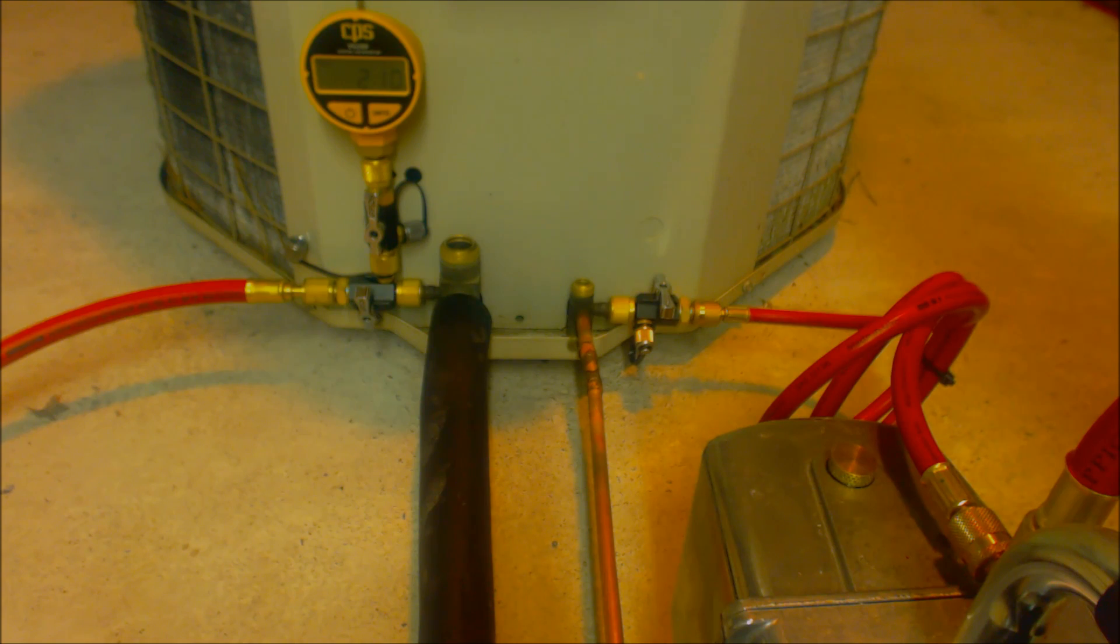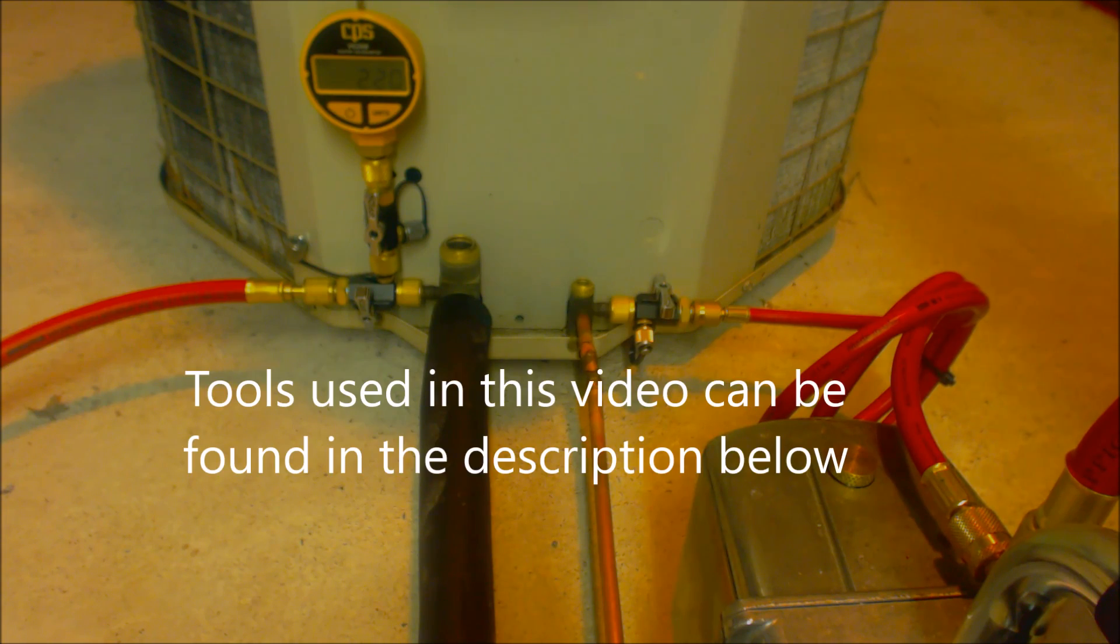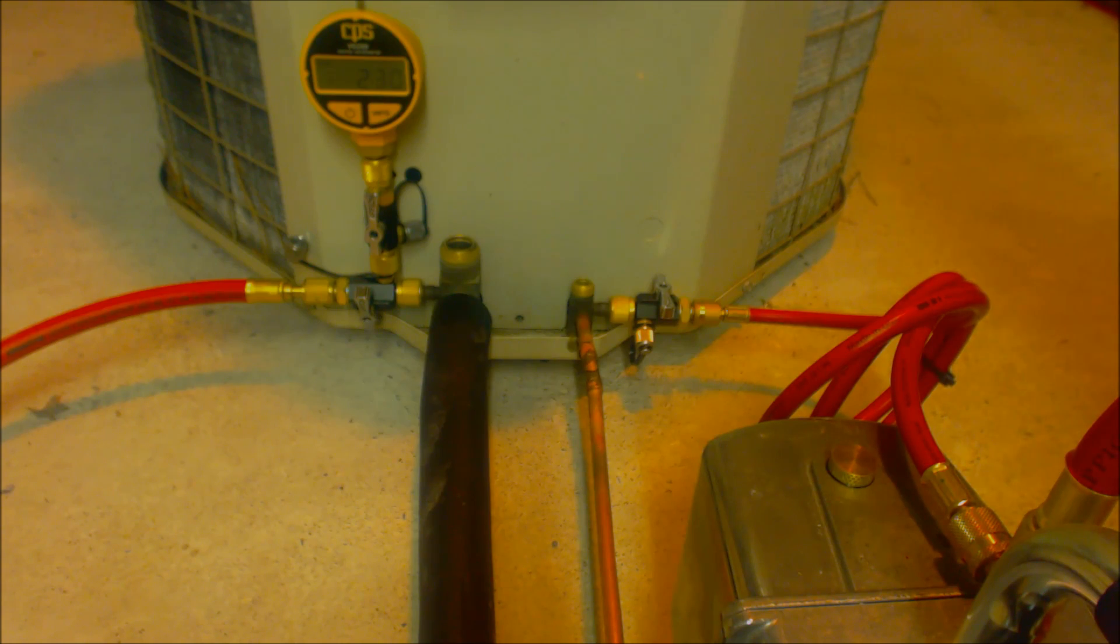If the micron level goes all the way up to a number that it can't read, then that's a definite indication that you have a leak. I usually pull my vacuums down to 200 or 300 microns and then make sure that they don't rise up above 500.